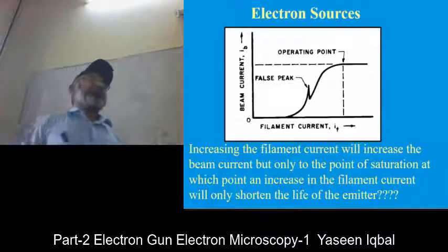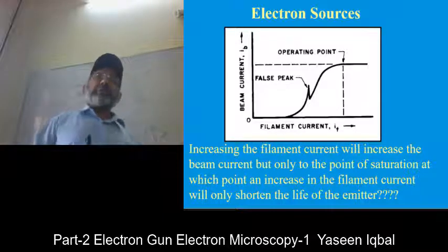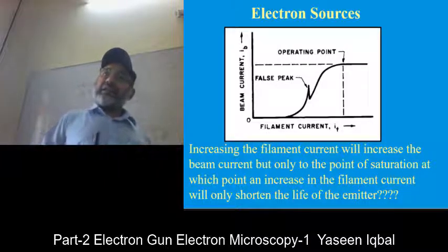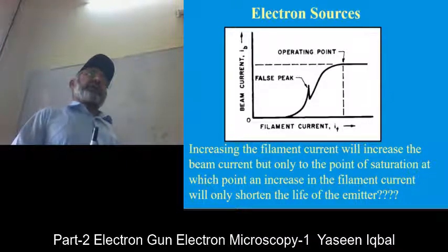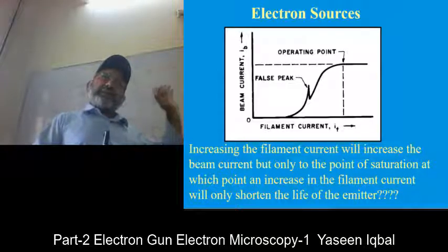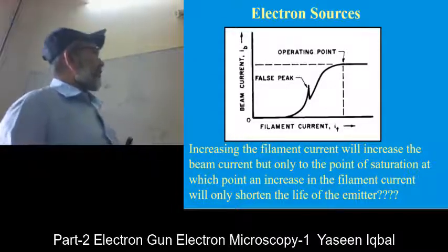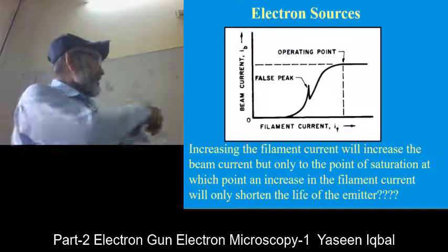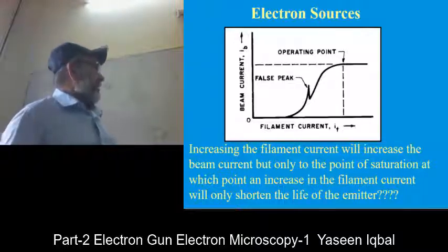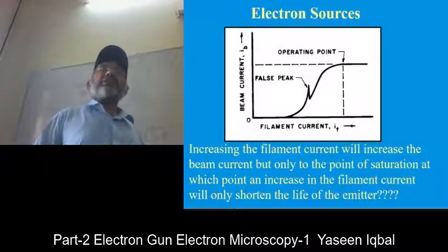Although they are nominal in comparison to the price of the microscope, they are still very expensive, so laboratories cannot easily afford the cost of buying guns time and again. When you are changing the gun, it obviously needs time, a technician, and vacuum as well, so people avoid damaging them. Increasing the filament current will increase the beam current, but only to the point of saturation, at which point an increase in filament current will only shorten the life of the emitter and will not give you any brightness.